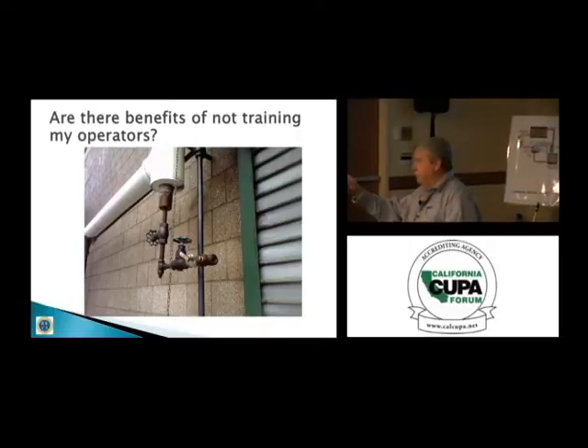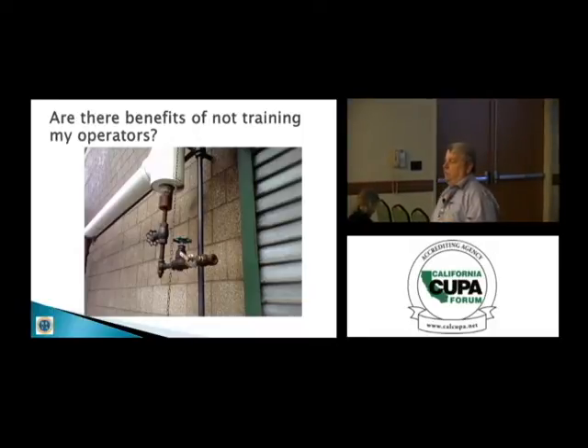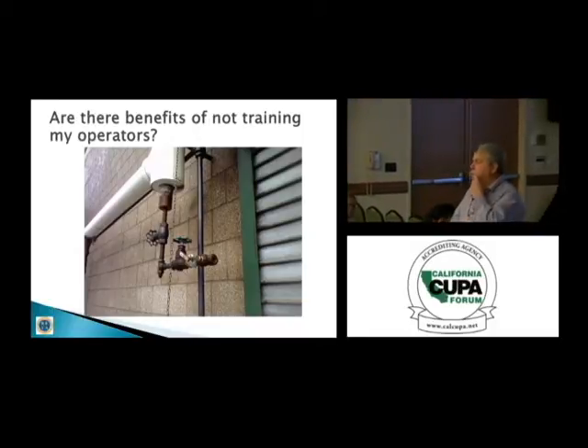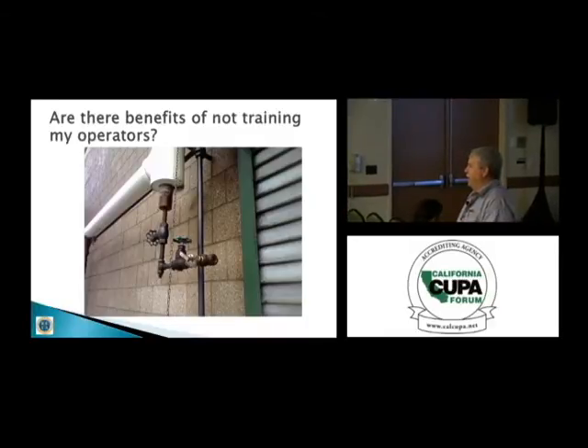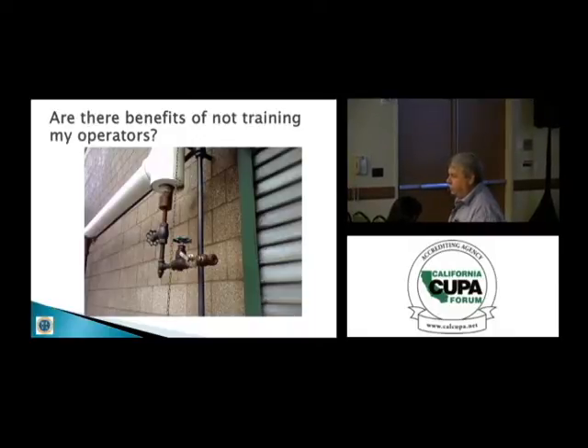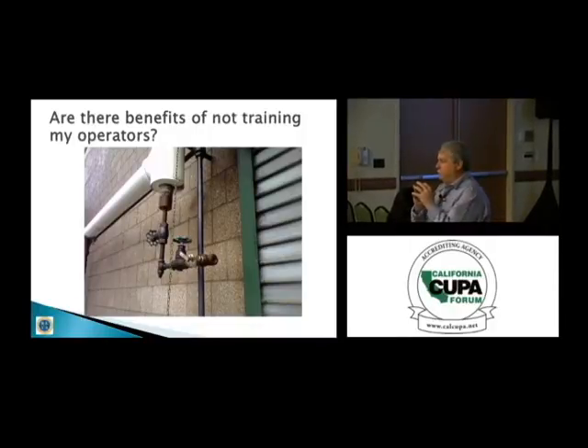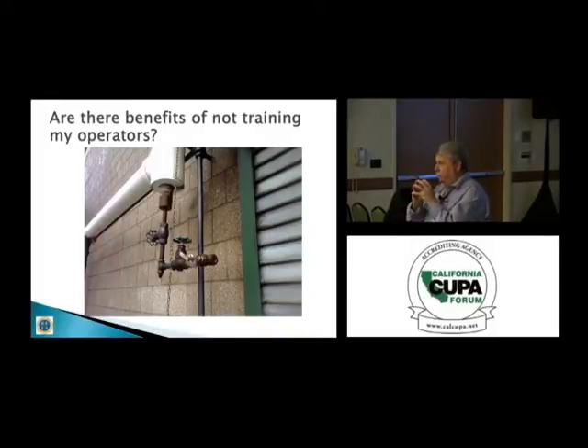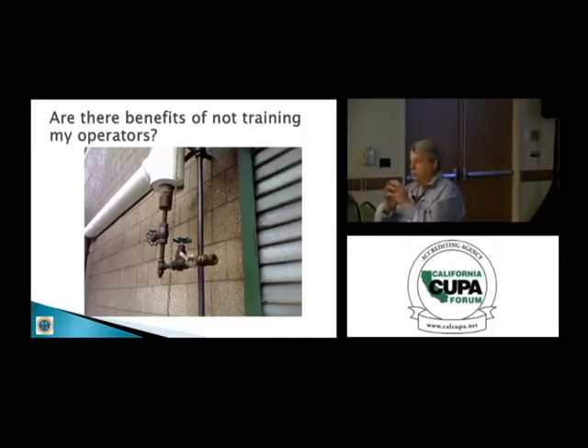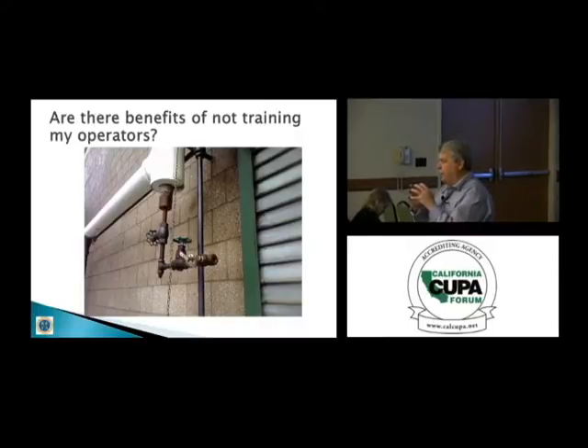When you ask the facility that you're supporting, do you have these things? And they say, yes, we do. Okay, great. Are they vented? The reason you're asking is that one of the dangers of trapped refrigerant is that if you trap liquid and it gets warm, it's going to swell. I'm not going to use the word expand, because expansion means something else to us in refrigeration, but it's going to swell. The density of the fluid changes with its temperature.